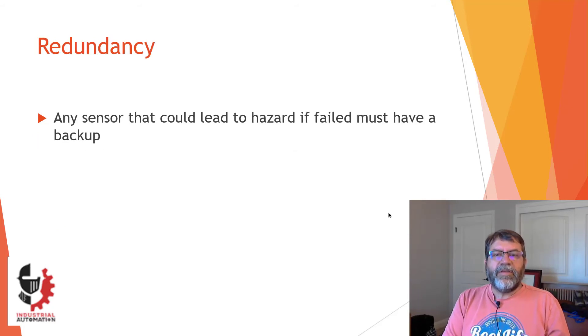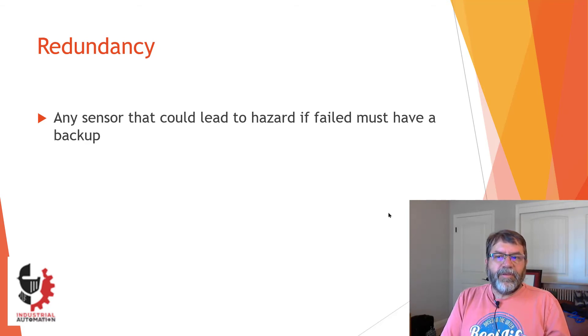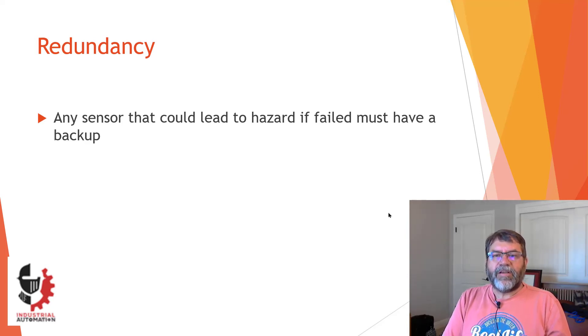Next is redundancy, and this one's pretty short and simple. Essentially, any time you have a sensor where a failure could lead to an unsafe condition, you have to put in a backup sensor — that's pretty well mandatory. If one sensor failure can lead to an unsafe condition, you have to have a backup sensor. Pretty straightforward.